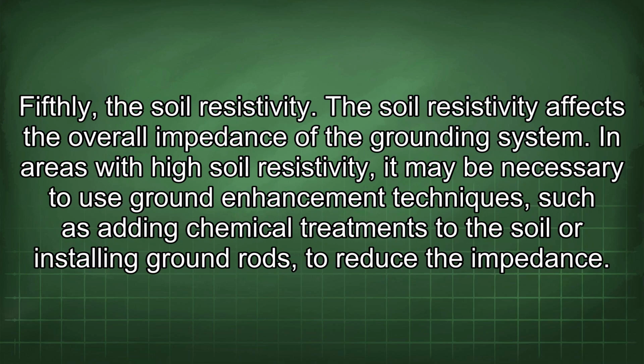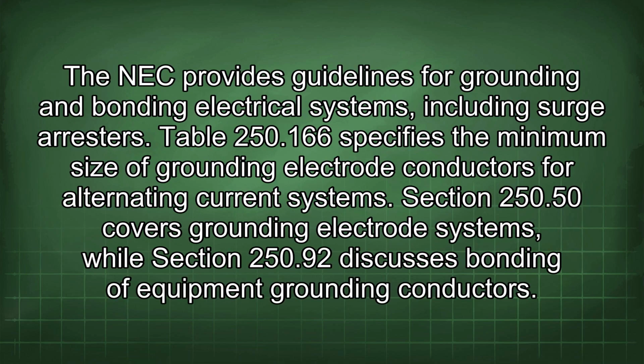The soil resistivity affects the overall impedance of the grounding system. In areas with high soil resistivity, it may be necessary to use ground enhancement techniques such as adding chemical treatments to the soil or installing ground rods to reduce the impedance. The NEC provides guidelines for grounding and bonding electrical systems, including surge arrestors.